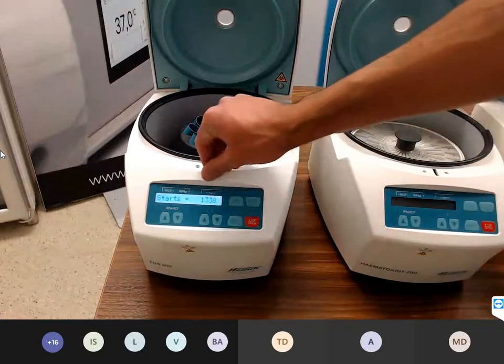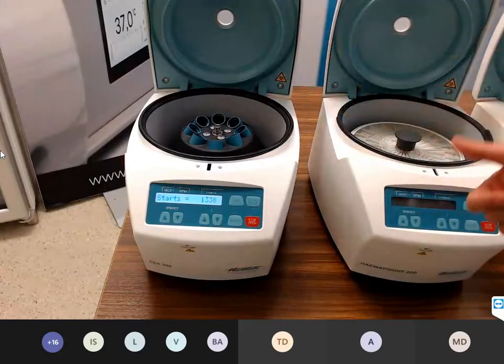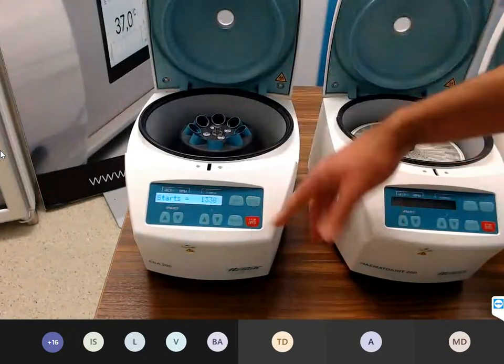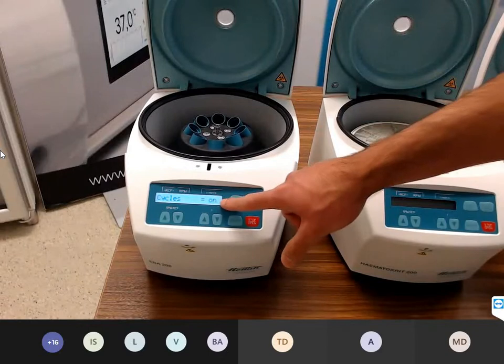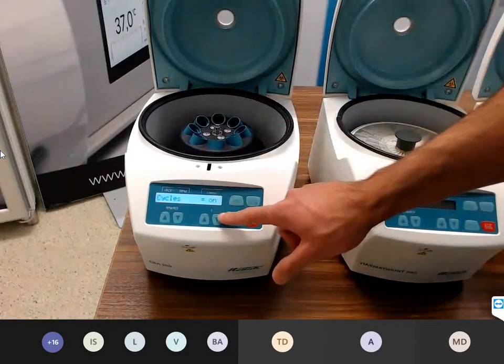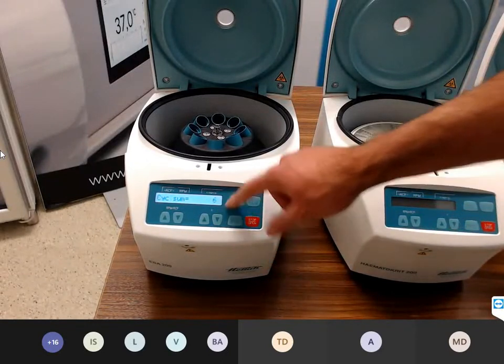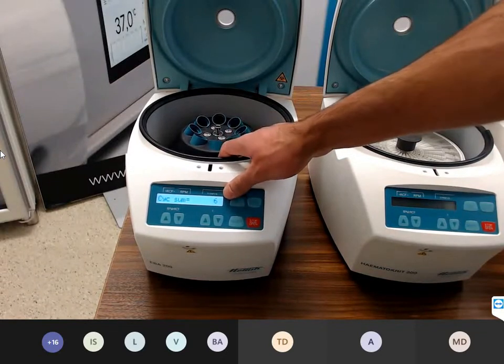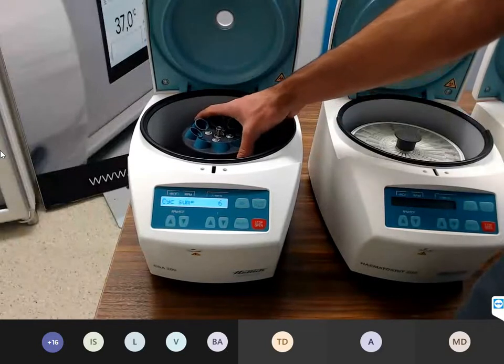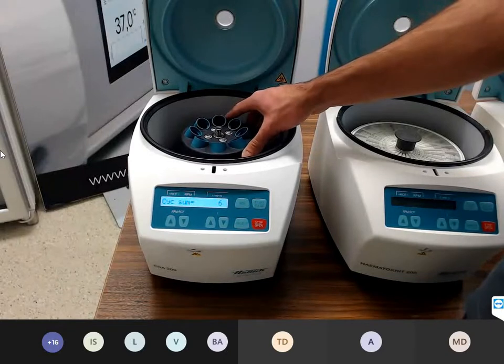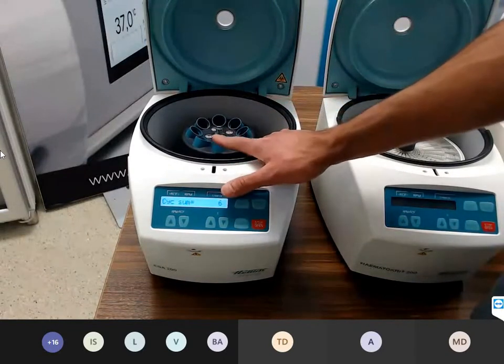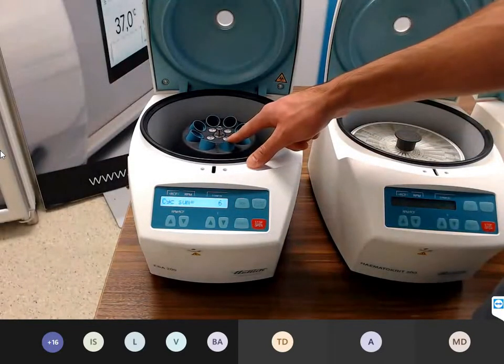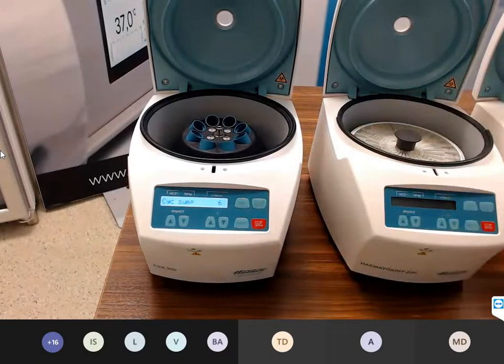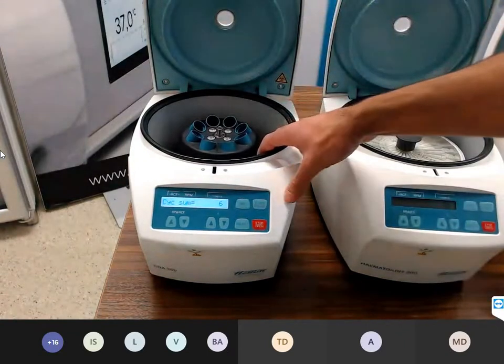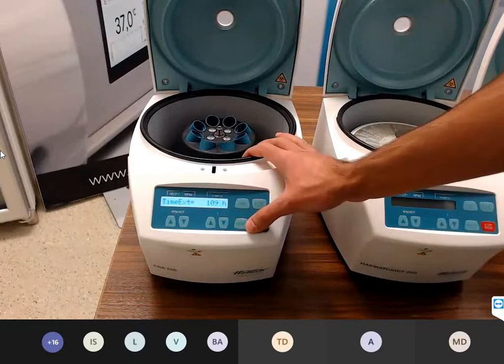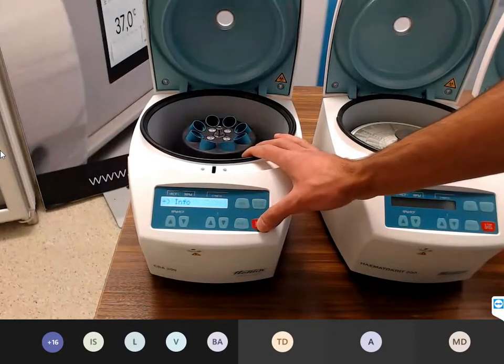We can read the starts. One start means close the lid, start the centrifuge, stop the centrifuge. This is one start. And we have a cycle counter on this centrifuge. You can switch the counter off or on. We can also read the cycles here on the display, very important. This is part of the maintenance. For example, we have the maximum cycles on the rotor, and we have to check the cycles like here. But that's part of tomorrow, the maintenance. This was the machine menu.